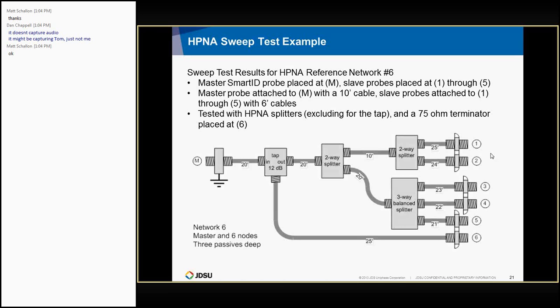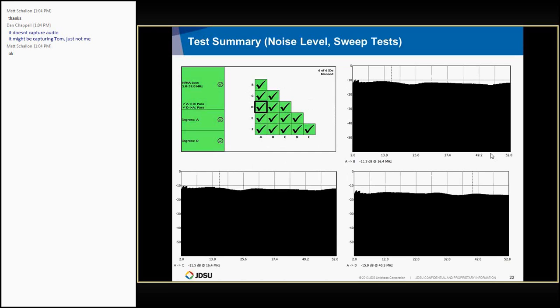So there's a 75 ohm terminator placed at the connection point labeled 6, so that you don't generate any reflections on that. And this is the output that you get. It's a clean network, so everything comes up green. The only thing you see is a little bit of variation in the loss.